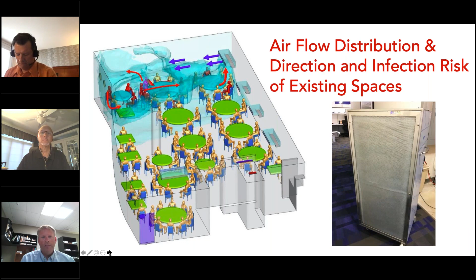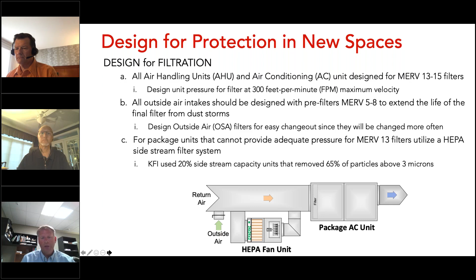Talk a little bit about new spaces. So with new spaces, obviously we can do a lot of different things. We can design the air handler system for MERV 13 or 15. We can design the filter racks for staying less than 300 feet per minute. We can put in outside air filters to pre-filter, to remove dust. So there's a lot of different things we can do on new systems that on existing systems, we have to be a little bit more creative on what we can do. But I bring up using side stream filtering as another way that we can put more filtration on an existing system without removing the existing air handler. Next slide.